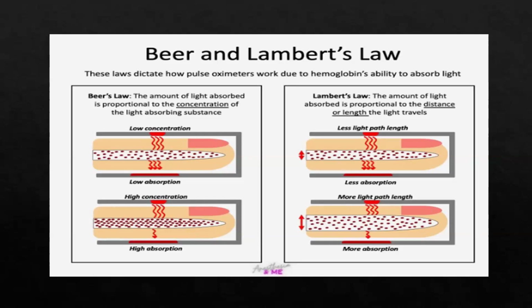Lambert's law. The amount of light absorbed is proportional to the distance or length the light travels. As we can see in the picture, in first picture, the amount of distance that the light has to travel is less. That is the reason the amount of light reaching the receiver on the other end is more. In the second diagram, as we see, the distance that the light has to traverse is more. That is the reason the amount of light absorbed by the tissue or the substance is also more, and hence the amount of light received by the receiver on the other end is less.